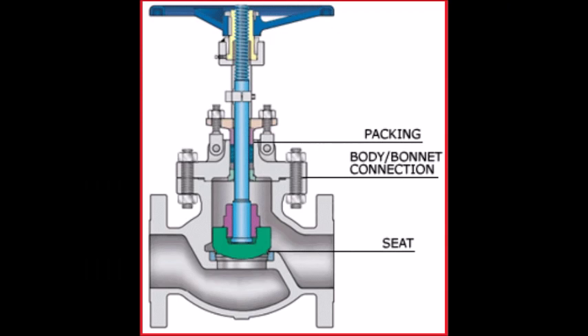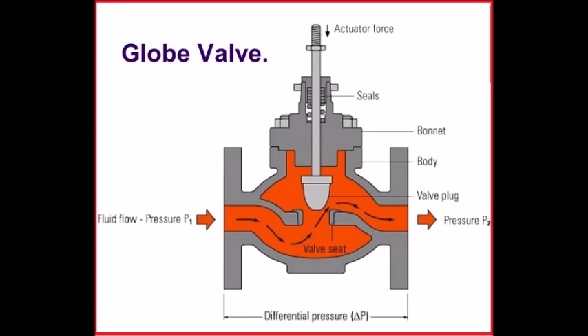Cage: The cage is a part of the valve that surrounds the plug and is located inside the body of the valve. Typically, the cage is one of the greatest determiners of flow within the valve. As the plug is moved more of the openings in the cage are exposed and flow is increased and vice versa. The design and layout of the openings can have a large effect on flow of material, the flow characteristics of different materials at temperatures, pressures that are in a range. Cages are also used to guide the plug to the seat of the valve for a good shut-off, substituting the guiding from the bonnet.